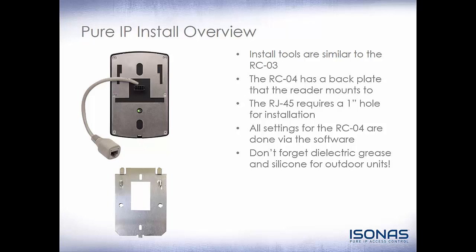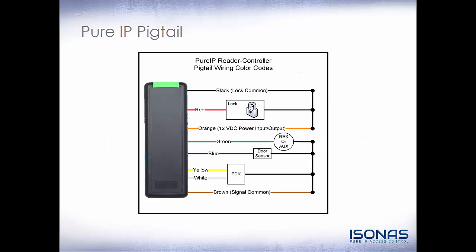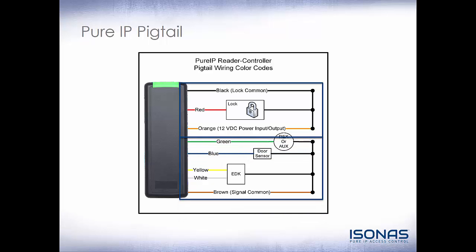Just because the RJ45 is on a longer whip to get it away from the back of the reader controller doesn't mean it's not exposed to the elements. Moisture will always find a way in, so make sure dielectric grease is applied to terminals. The Pure IP pigtail has been simplified: red and black go directly to our lock if we're not using an EDK. Orange and black is our static 12 volt DC for request to exit motions and other peripheral devices at the door. Our two inputs are similar to the RC-03, except brown is now our signal common. Green is request to exit or auxiliary, and blue is our door sensor.